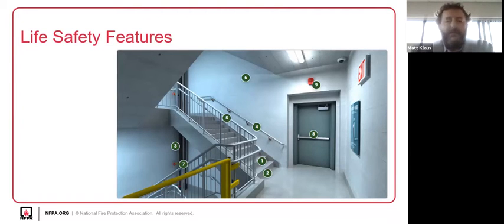The other part is the active system components. Near node number 3, you might have a standpipe, and the fire department might come in there, not just to get people out, but to make a hose connection and start manual firefighting from that point, because that stair enclosure is passive construction, passive fire protection, but rated and safe. That's a place they know they can set up operations, but not if we've got people, boxes, ladders, or stored goods in the way. So we really have to be careful about these life safety systems, and not just assume the sprinklers will take care of everything. The whole thing works together, and we've got to be aware of that.